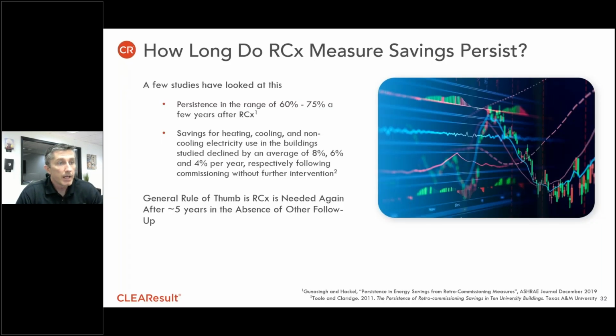There have been a few studies looking at how long savings persist through retro-commissioning measures. One study published in the ASHRAE Journal found persistence in the range of 60 to 75% a few years after retro-commissioning was performed. Another study I was personally involved with, looking at university buildings over a long period, found energy savings declined on average by 8% down to 4%, depending on heating, cooling, or non-cooling electricity use, in the absence of further intervention.